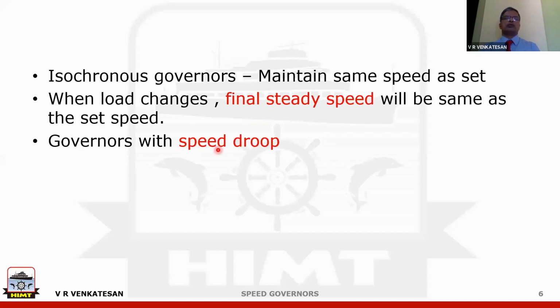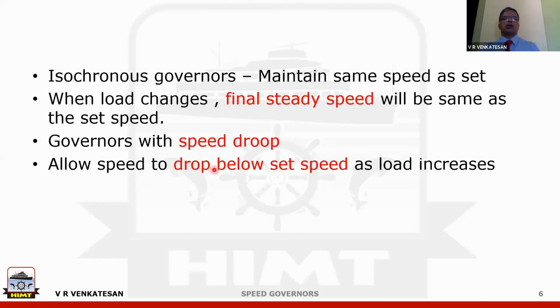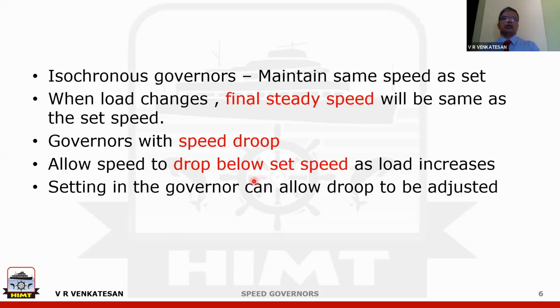If you have a governor with speed droop, the difference is that it will allow the speed to drop below the set speed as the load increases. As the load on the engine keeps on increasing, the actual speed will become lower. That is called a governor with speed droop. There is a setting in the governor which will allow you to change the droop. There is a droop adjustment in the governor. All the engineers who sailed on board would have seen this. So there is a droop adjustment which we can adjust as required.